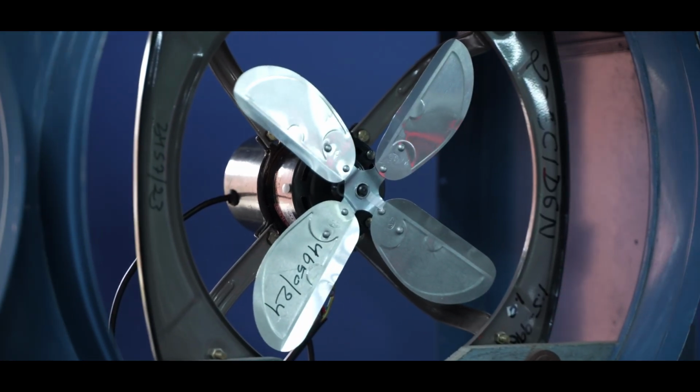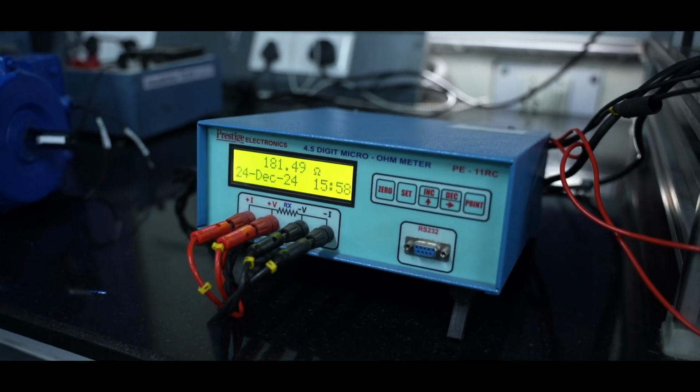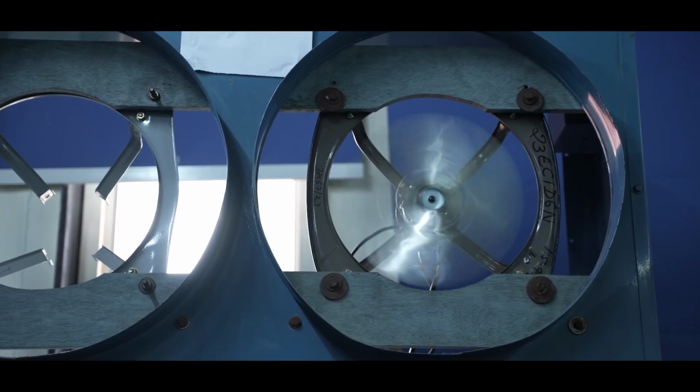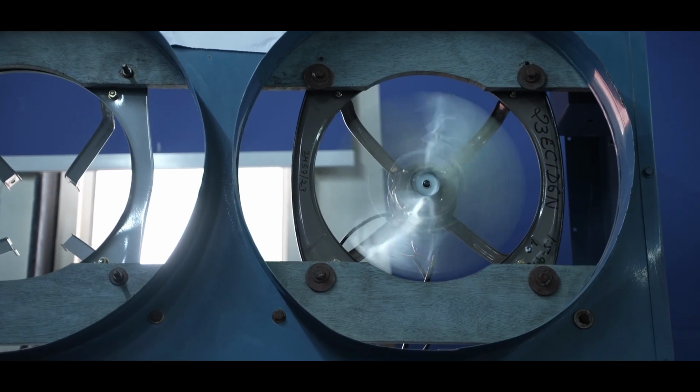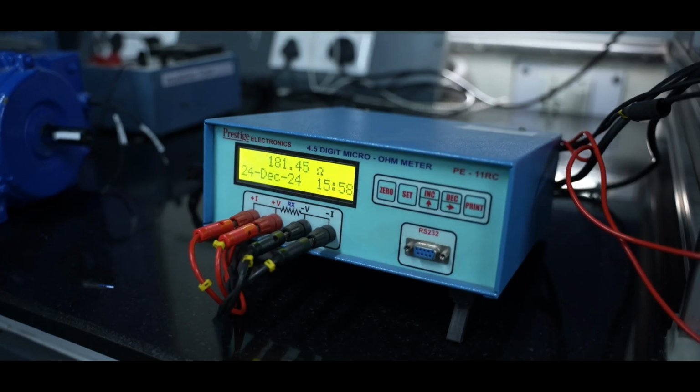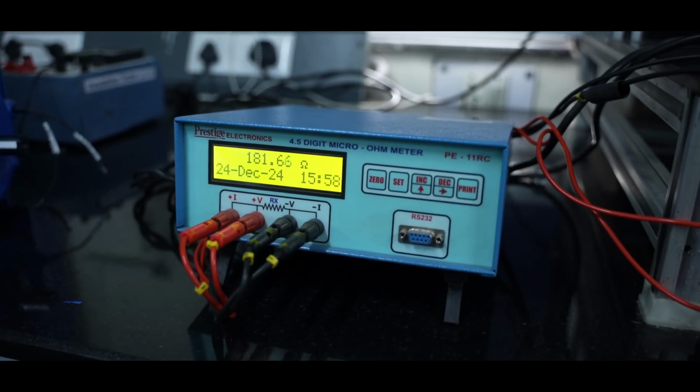Temperature rise test, Clause 12.2. Excess heat can degrade a motor over time. This test monitors how much the motor heats during continuous operation. In this test, the motor is operated under load until a steady state is achieved. The temperature of the winding is then calculated by comparing resistance measurements before and after the test.